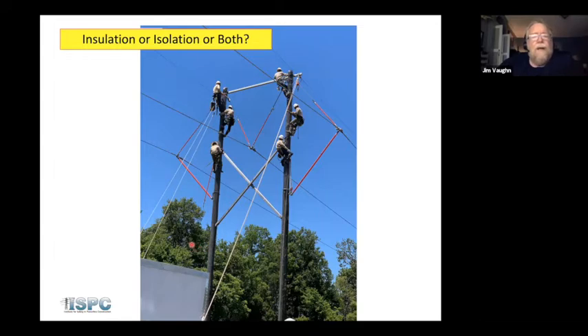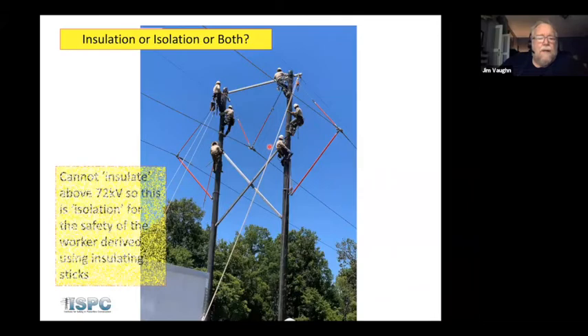The issues that come in here are how we rig and where the linemen are going to be on the structure. When you get into the lower voltages like 69 and 115, it's possible for a lineman to be inside of the pole and be within the MAD of the conductor. Now, there's a very real risk there when we get into high voltage conductors associated with TOV. And we're going to discuss that at length in a minute, about what TOV is and why we have to be concerned about it. But these guys have this laid out well. They're positioned well on the pole, and this is actually a pretty good one.